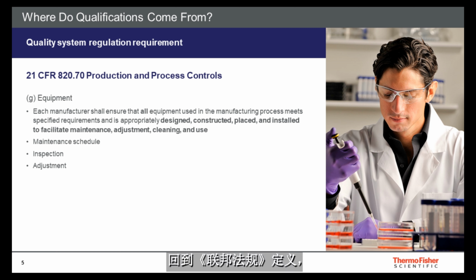Moving back into the CFR definitions, if we dig deep into 820.70(g), it defines the essentials of what equipment performance needs to be documented. As before, I have highlighted the pertinent language that guidance interprets for industry. Again, it's not calling out the IQ, OQ, or PQ mechanism, but rather what needs to be documented. I have called out the subsection specific to manufacturer requirements for maintenance, inspection, and adjustment of equipment. Implicit in each of these is documentation.